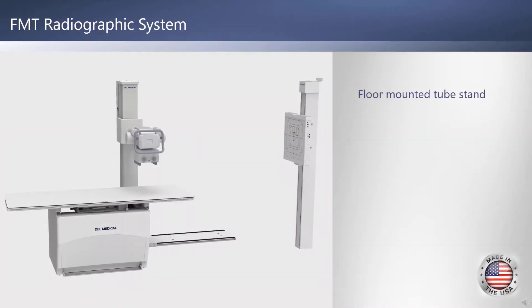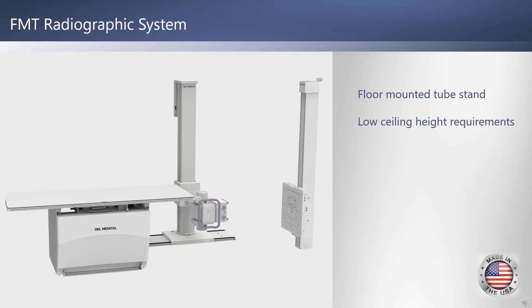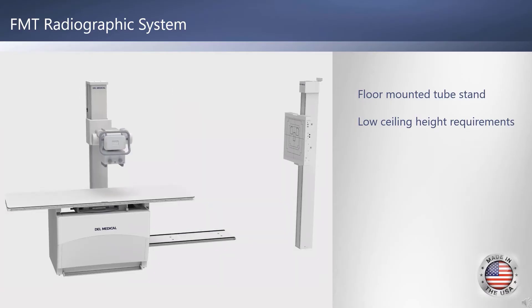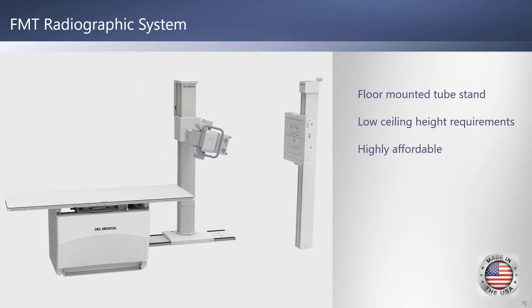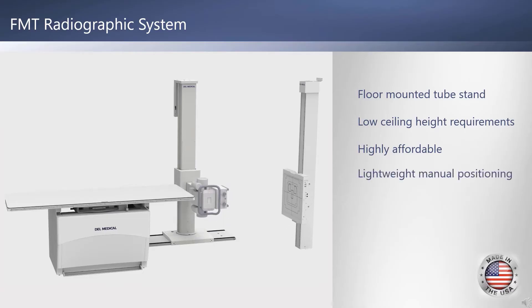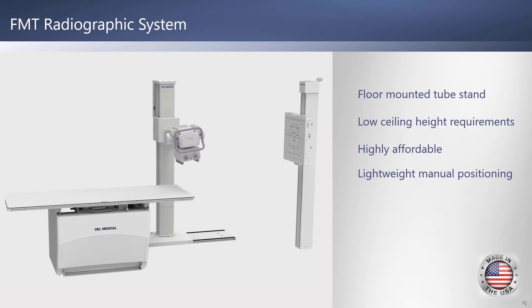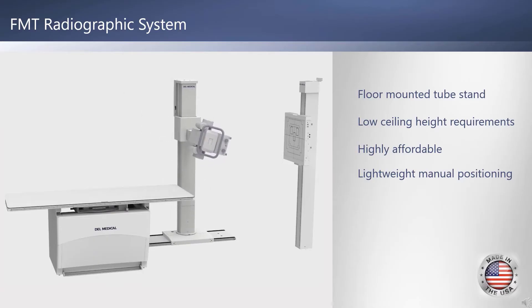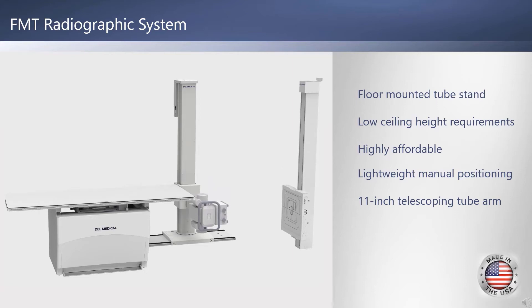The Del Medical FMT's tube column is installed on a low-profile floor-mounted track. The FMT has a very low minimum ceiling height requirement of just seven feet three inches. Like the FWFC, the affordable FMT eliminates the need for costly ceiling support modifications. The tube travels effortlessly along the longitudinal axis of the table and displays the SID and tube angle for added convenience. Eleven inches of telescopic travel provides additional imaging flexibility.